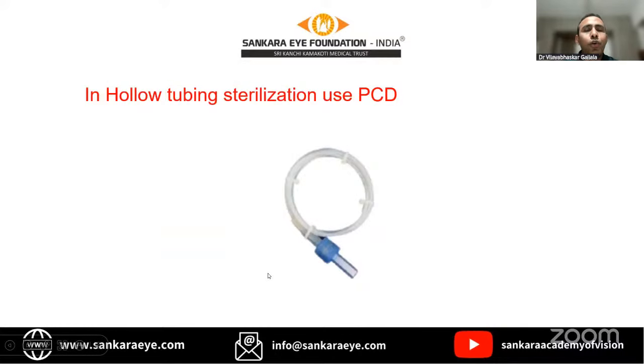And whenever you're using hollow tubings, as I mentioned, we will use a lot of hollow tubings. How to confirm the moisture is able to penetrate through the complete tubing, that hollow structure, and sterilize the inner surface too? For that, we'll use PCD, that is process challenge device. Here we are challenging that process. In PCD, it's a long tube. At one end, there will be an indicator. If the moisture is able to pass through the complete tube and reach the other end, there will be a change in the color of this indicator. That indicates that the sterilization process is effective in sterilizing the inner surface of this hollow tube.